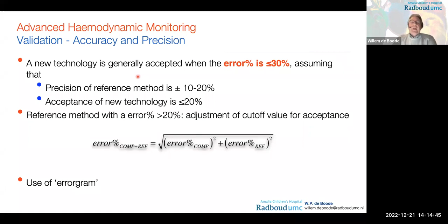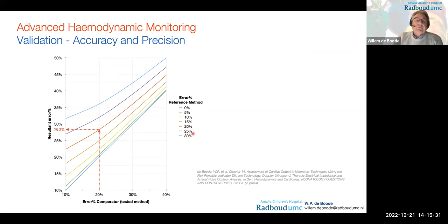And as it's put out in this errorgram, here you can see the error percentage of the comparator, so the tested method. This is the reference method. So if you want to have, the red one is the 20%, and if you get 20% for both methods, it will give you 28.3%. So that's why for a clinical situation, 30% is regarded as acceptable for the error percentage. But as said, if your reference method is not that good, you have to adjust that acceptable range.